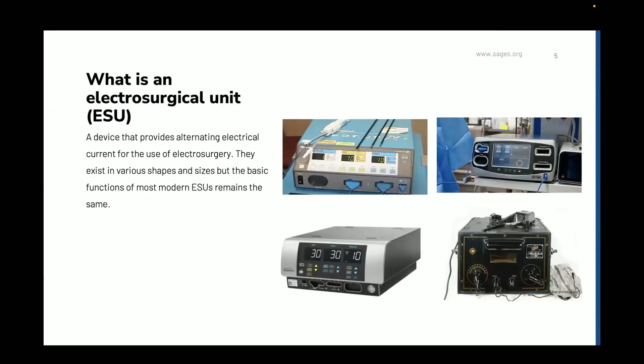So what is an electrosurgical unit? The blue box in our ORs. This is a device that exists in many shapes and sizes, but essentially it serves the same function, which is to convert the low frequency energy that we get out of our wall sockets, in North America about 60 hertz, into a high frequency voltage, typically 300 to 500 kilohertz. This is the optimal frequency to achieve the desired tissue effects. It's also a higher frequency than would depolarize our patients' muscles and nerves, which we certainly wouldn't want during surgery.